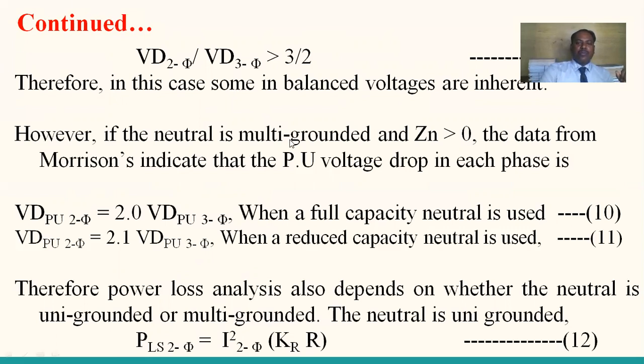However, if the neutral is multi-grounded, in the sense that it is grounded at many places, and Zn is greater than 0, the data from Morrison indicates the per unit voltage drop in each phase. This is the reference taken from the IEEE papers. Voltage drop per unit of a two-phase system is equal to 2 times the voltage drop per unit of a three-phase system when a full capacity neutral is used. This is equation number 10. And the voltage drop of a two-phase system per unit is equal to 2.1 times the voltage drop per unit of a three-phase system when a reduced capacity neutral is used.